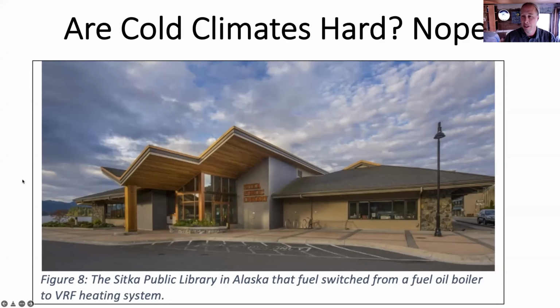They got rid of their expensive, difficult to work with fuel oil, which is diesel, and put in a VRF, called variable refrigerant flow. It's a big heat pump that sends a big tube of refrigerant to a manifold, and that manifold spreads out like a little octopus of smaller refrigerant lines going to ductwork or radiant panels or whatever the actual heat distribution part is. Anyway, they put in a big VRF—a cold climate heat pump—and that's how this Alaskan library is heated and cooled.